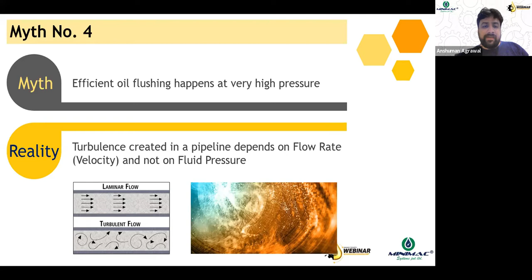So this is a big myth that high pressure actually performs good flushing, but that's not the case. High pressure would just help you to check the leakages. It would help you check the integrity of your pipeline, but it would not help you in any manner in terms of flushing. But yes, what happens during flushing is a lot of back pressure is created. Because of the larger flow rate going into a smaller cavity, back pressure also is increased. So in order to sustain that back pressure, you do require high pressure for your motor or the pump capacity or power, which you're using for performing the flushing application. So in other words, you can say that for good flushing to happen, you require both flow rate as well as pressure.